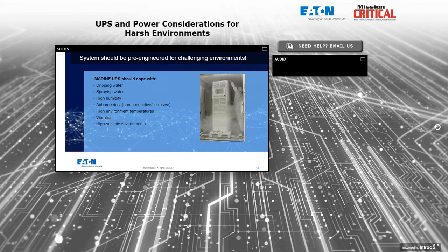So it's important that the temperature environment and the overload capacities are considered and make sure they don't interfere with each other. Marine UPSs, as you can imagine, should be able to cope with dripping water, spraying water horizontally, high humidity conditions, airborne dust that might be corrosive, significant vibration in shipboard applications, significant tilt in small boat applications, might tilt more than 10 degrees, for example. Anything more than that would be a pretty violent environment for the people on board beyond just the UPS. But those are things to be considered. Most UPSs are not designed to tip more than 10 or 15 degrees without risking some dislocation of componentry inside.